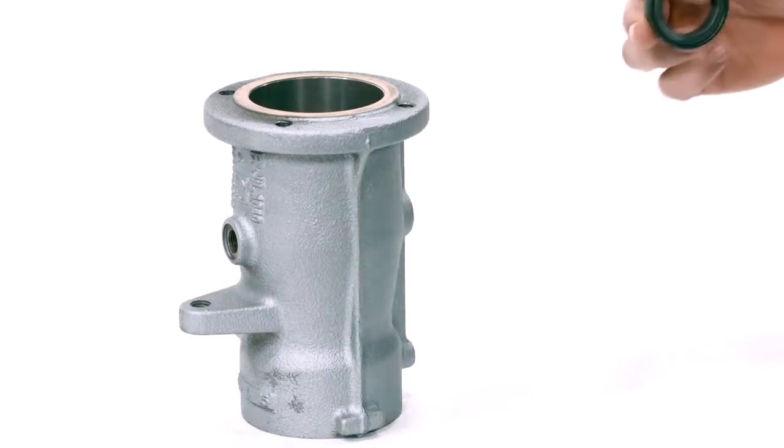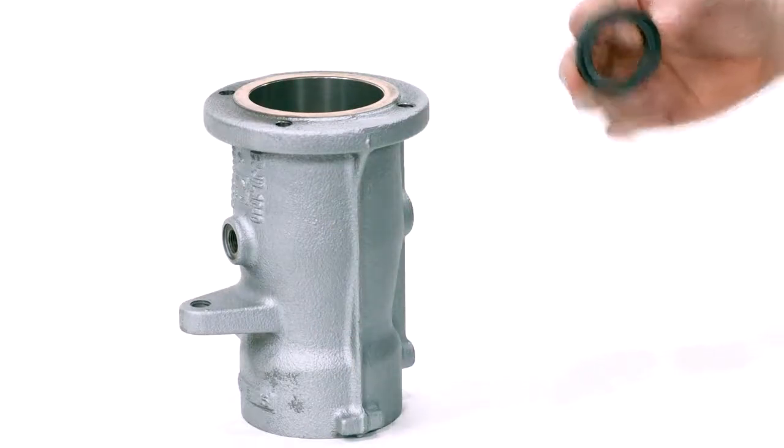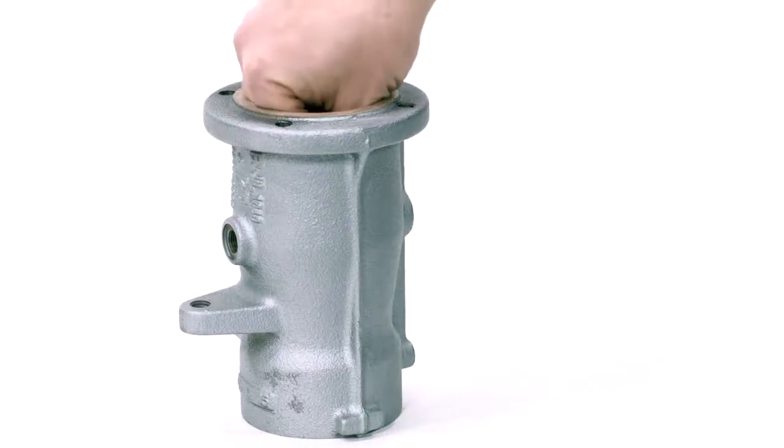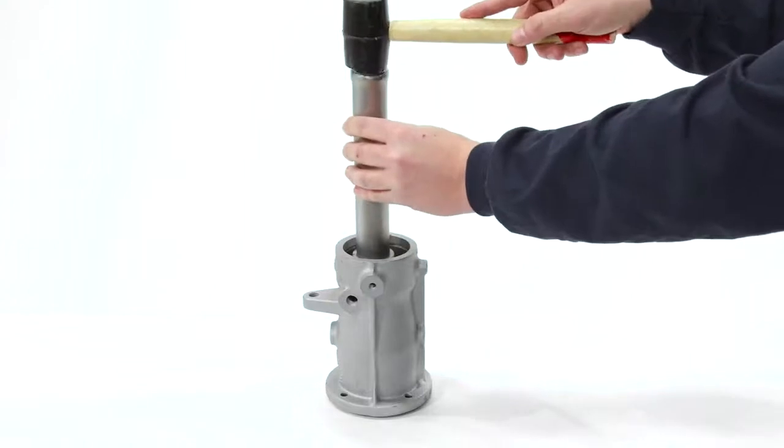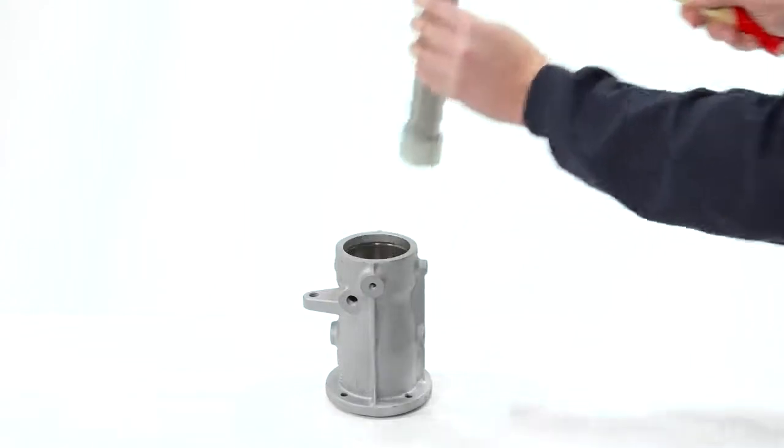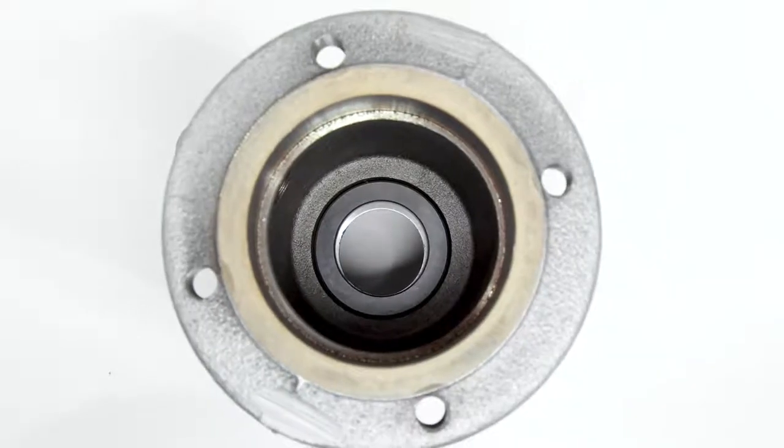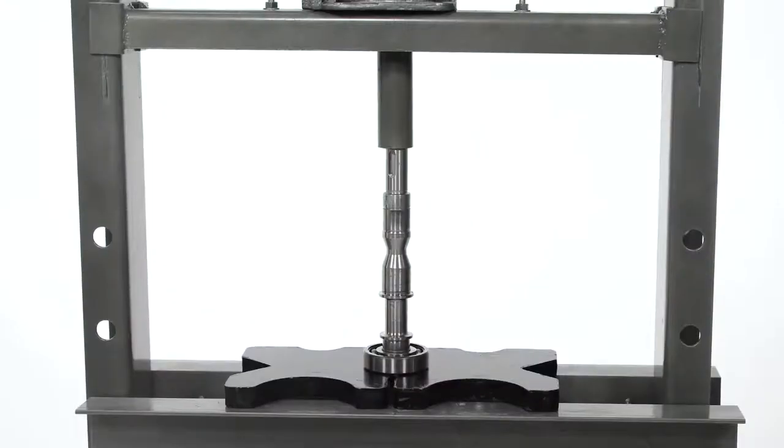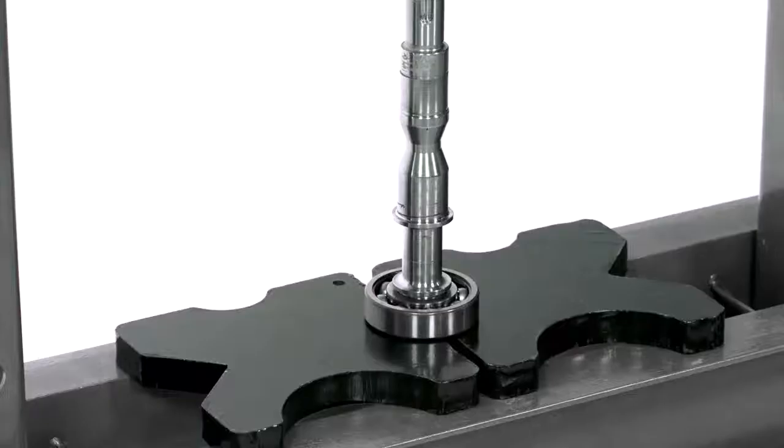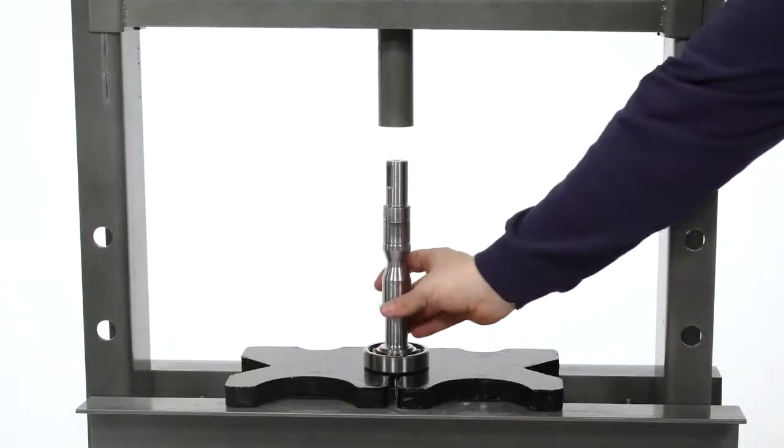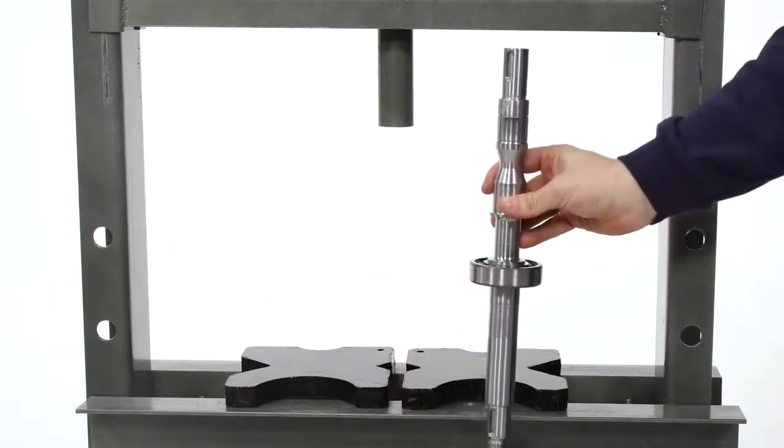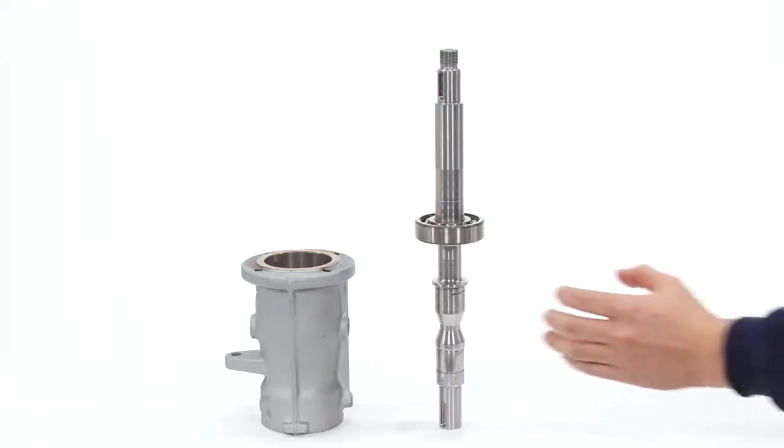Lubricate and install the stationary face of the mechanical seal and o-ring. Press the bearing onto the pump shaft on the impeller side. Install the bearing snap ring.